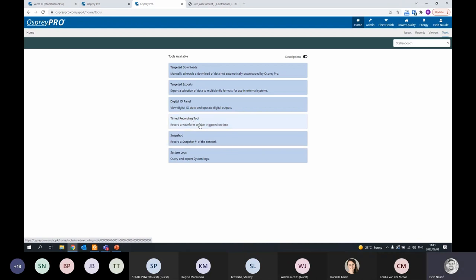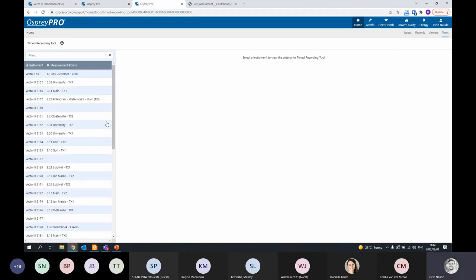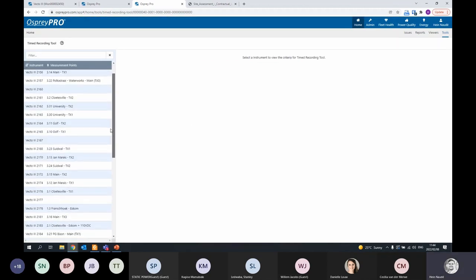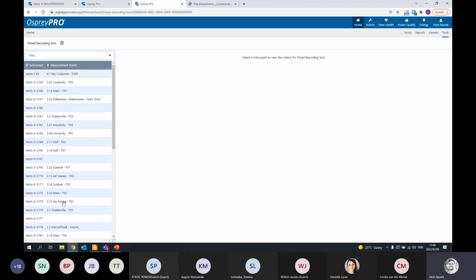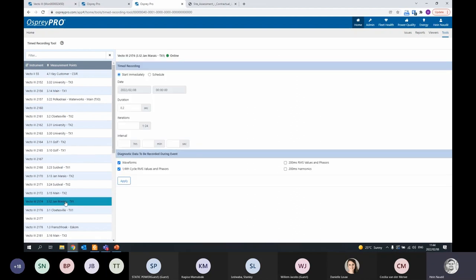So as an example, let's say I want to do a timed recording. I can select the specific point I want to do a timed recording for. So let's select that specific measurement point. You can then specify whether this recording should start immediately or be scheduled for a specific time. So if I start this immediately, I can select the duration.